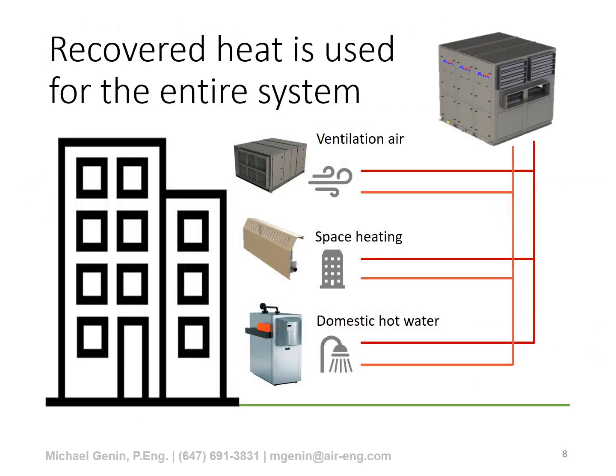The major advantage of this system, when we talk about decarbonization, is that we can now use our exhaust air as the source of decarbonization. As soon as we make hot water, we can use this heat in every part of the building. We can use it in the ventilation air, for space heating, perimeter heating, radiant heating, and we can also use it to generate domestic hot water if we so choose.